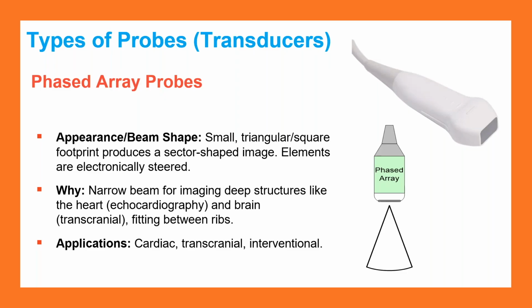It also has to penetrate a long ways, which means we're talking primarily lower frequency. 1 to 5 megahertz is pretty common on this one. Okay, 5 being pretty high frequency for a phased array probe. And between the image shape and low frequency, it's probably the worst image quality out of all probes. So you really struggle when you're using an ultrasound phantom to get a good image quality. Okay.